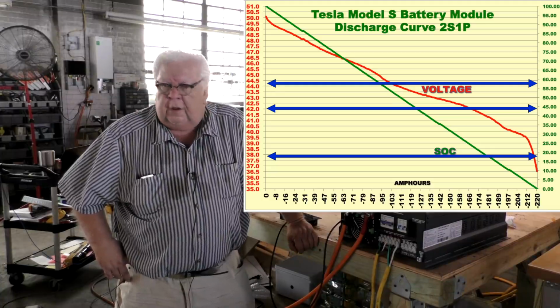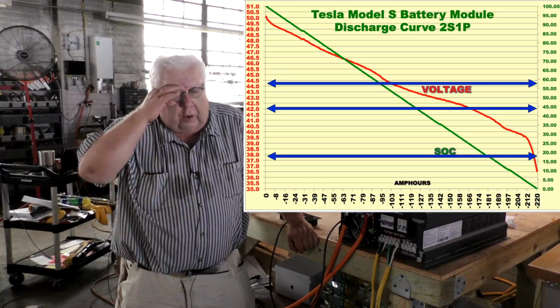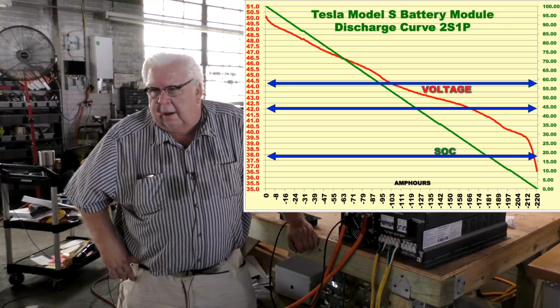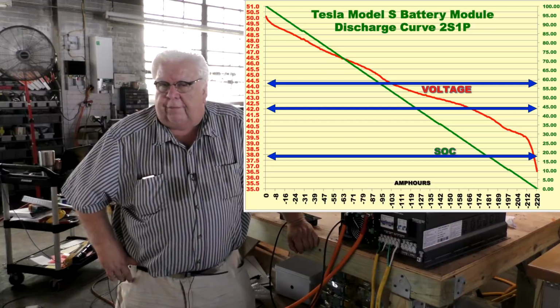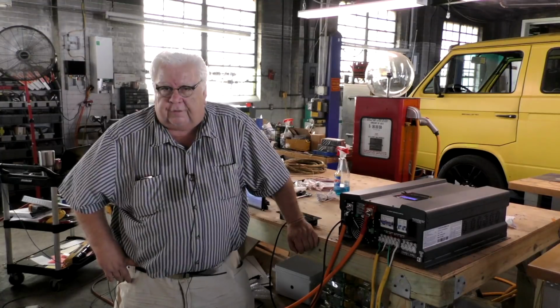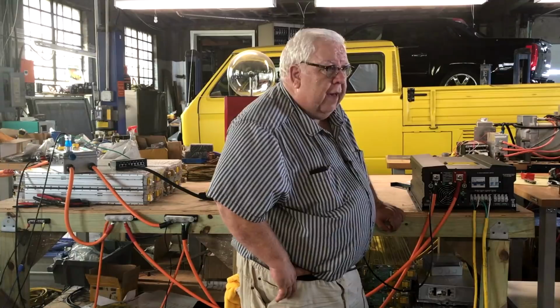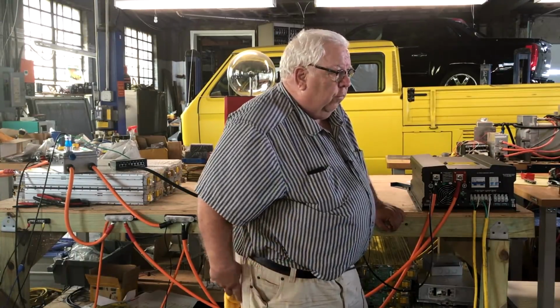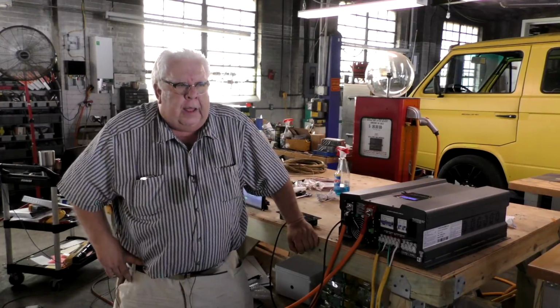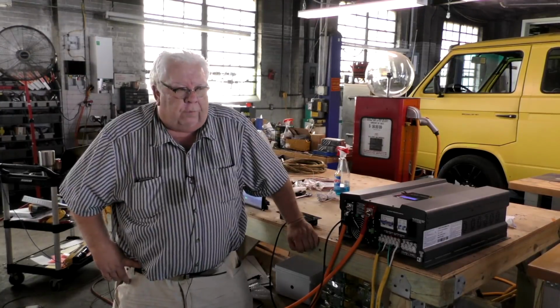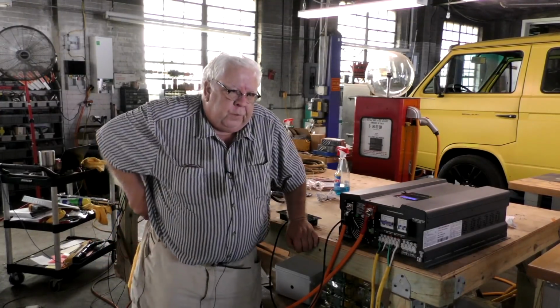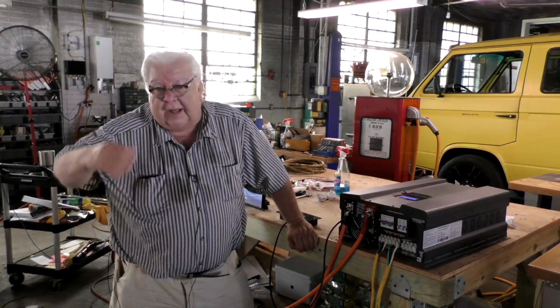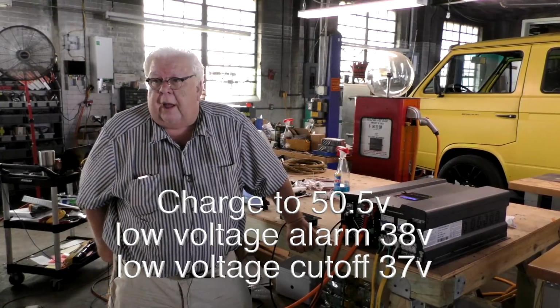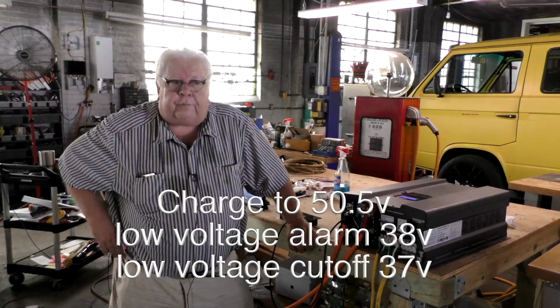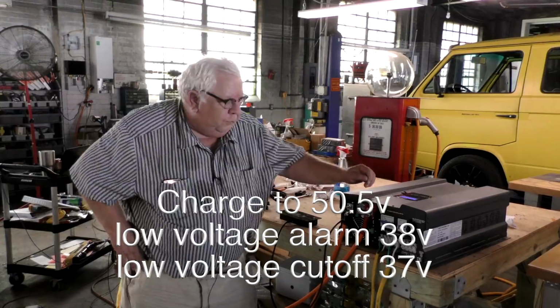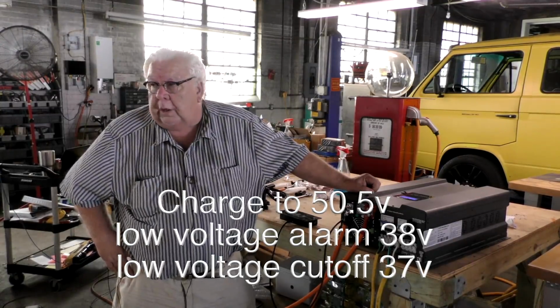And then if you use them to charge, you have to make some provision to shut it off, and that often interrupts your power, and it's just a kind of a shit show of trying to get this equipment working with Tesla battery modules. It's simply not designed for the fairly unusual voltages we have, using 6 cells in series at 3.6 volts nominal. I found a group in China that makes a low-frequency transformer-based inverter for 48 volts that I really like. And we have negotiated with them to make a battery selection for their inverter that matches exactly the voltages I give them to work with a Tesla Model S battery unit. We've gotten the first ones of those in, and I am totally delighted with them.